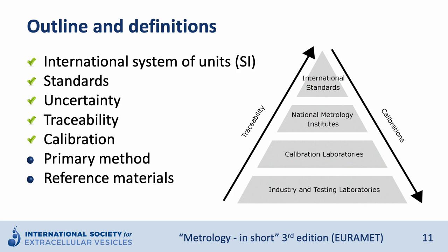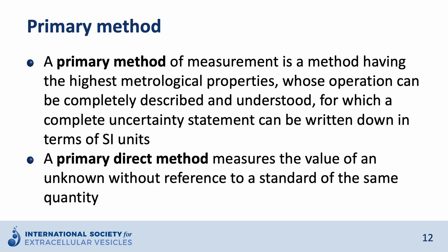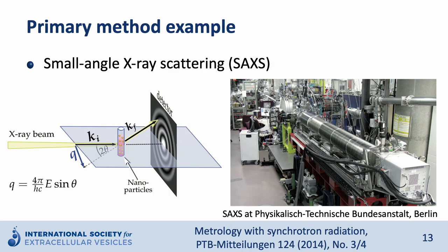I would like to introduce the term primary method, which can be used to produce reference materials. A primary method of measurement is a method having the highest metrological properties whose operation can be completely described and understood, and for which a complete uncertainty statement can be written down in terms of SI units. A special group are called primary direct methods, which measure the value of an unknown without reference to a standard of the same quantity. As an example, for the size characterization of nanoparticles, small angle X-ray scattering or SAXS can be used. In SAXS, a monochromatic X-ray beam hits the nanoparticle sample in solution, and from the scattering pattern the size of the nanoparticles can be determined with stated uncertainty. On the right you can see a photo of a SAXS beam line at PTB, the German Metrology Institute.